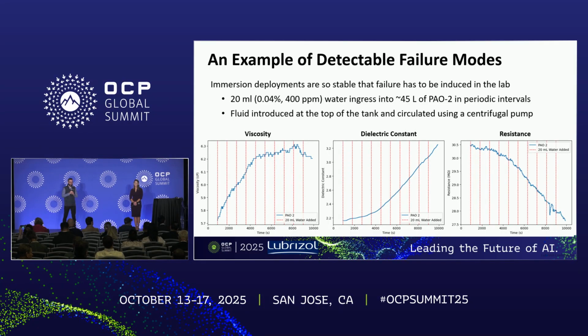in situ sensor. And you can see very clearly viscosity, dielectric constant, resistance, they move all in the directions that you would expect them to move. Viscosity, for instance, when you get enough water in there, you can start getting entrained droplets, and that can actually increase the viscosity, even though water is a little bit less viscous than most of the oils here. Dielectric constant and resistance, right? Those trend upward and downward as you might expect. But it's a strong message that yes, we have flat lines, but also we can detect when the line goes a little bit askew on us.